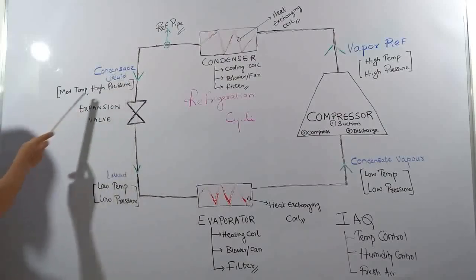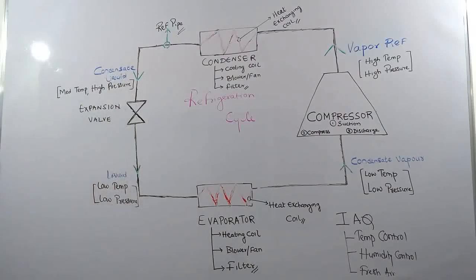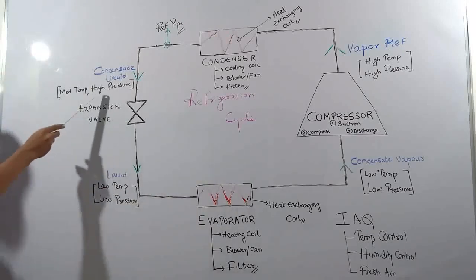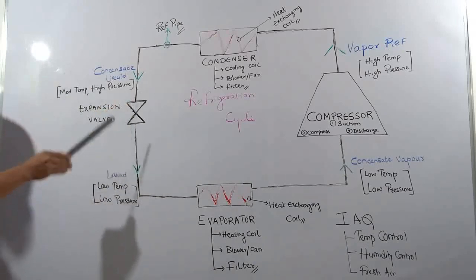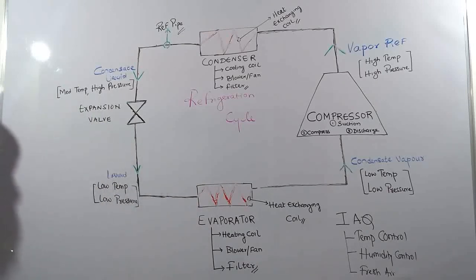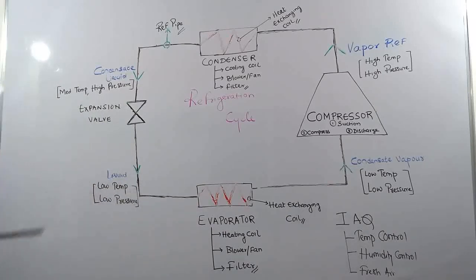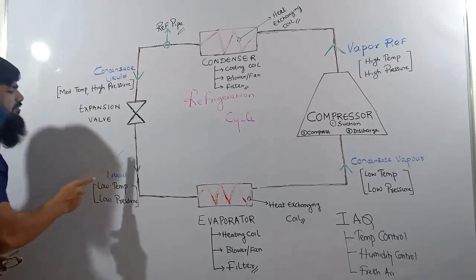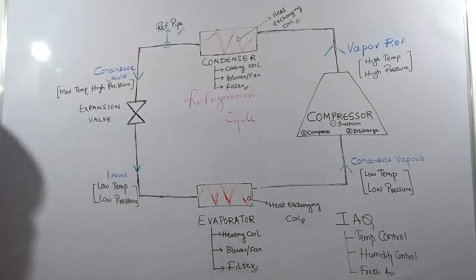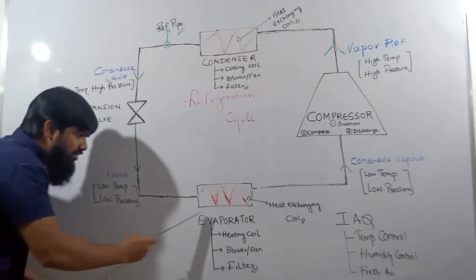The condensate liquid, which is at medium temperature and high pressure, is given to the expansion valve. The expansion valve reduces the pressure of the refrigerant coming at high pressure from the condenser. As the pressure decreases due to the expansion valve, the condensate liquid converts to low pressure, low temperature liquid - approximately at a temperature of 5 to 6 degrees Celsius, in liquid state. From the expansion valve, it is given to the evaporator.